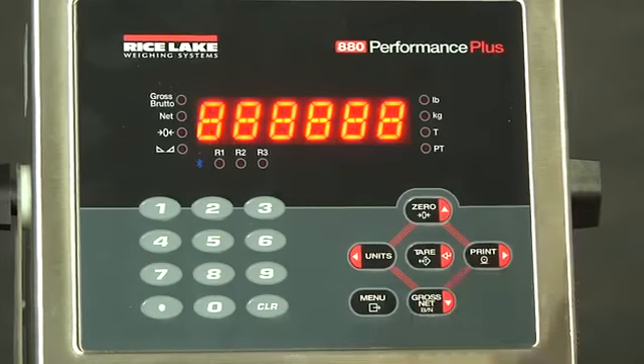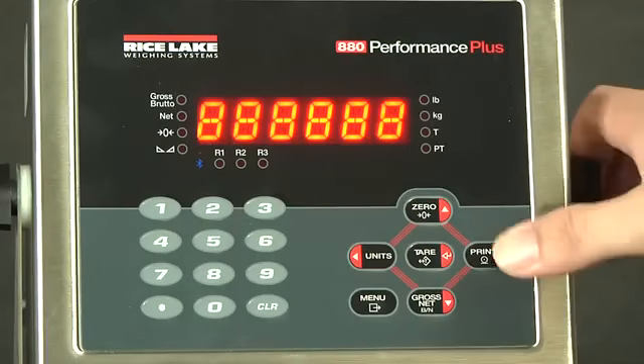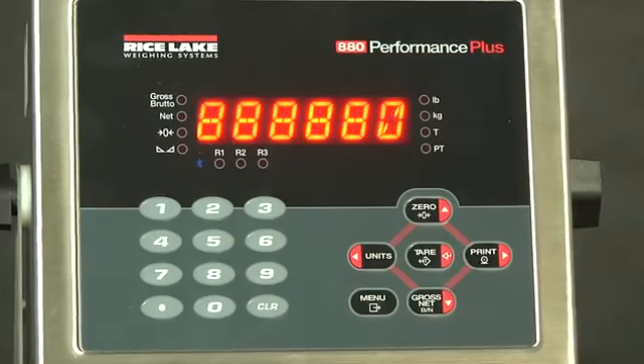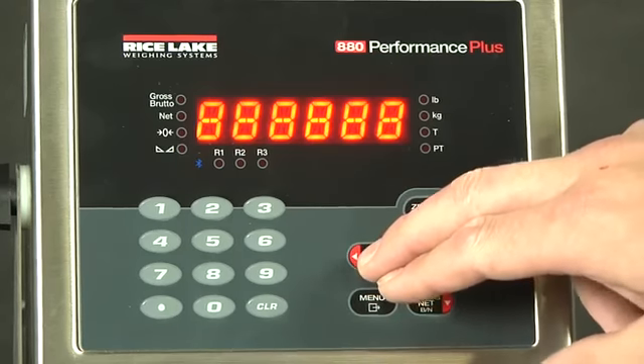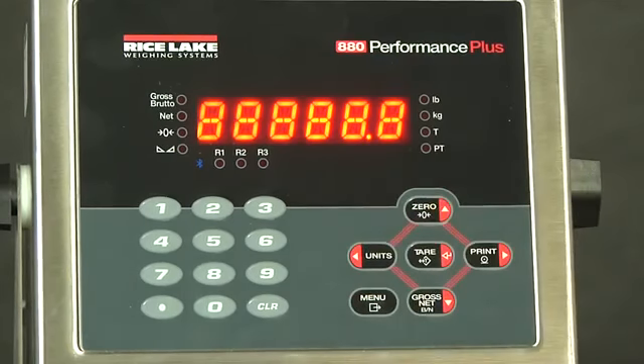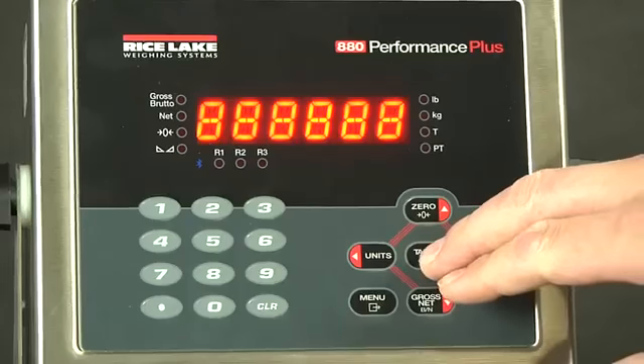If we drop down again, as you can see, there is currently no decimal point available. If we scrolled to the right, we could get 0 if we wanted to count by 10, 20, or 50 pounds. Or if we go to the left, we get 0.8, which actually indicates point of whatever division size you have. So we would count by 0.1, 0.2, or 0.5. That can be pounds, kilograms, whatever your units happens to be for the primary divisions. So, as it was already set up the way we needed it, we will accept this.